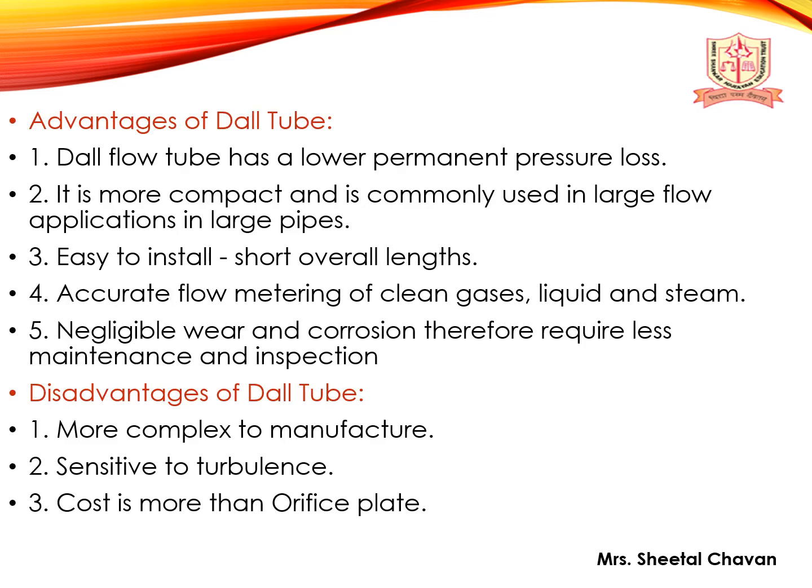Now let's see what are the advantages of the Dall tube. So the Dall tube has a lower permanent pressure loss, it is more compact, and it is commonly used in large flow applications in large pipes. It is easy to install, has a short overall length, and it accurately meters the flow of gases, liquids and steam. Negligible wear and corrosion, therefore it requires less maintenance and inspection.